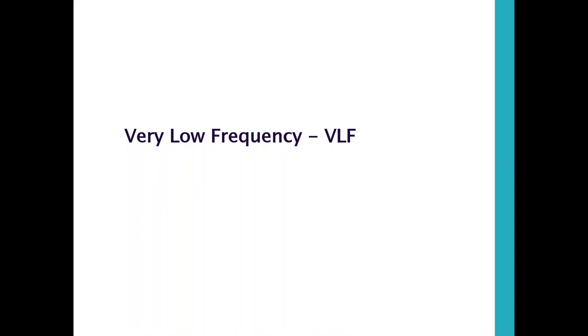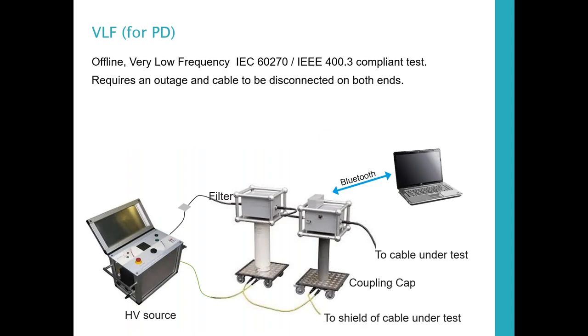So we're going to look at, at this point, some direct-connected offline testing. And we'll start off with the very low frequency VLF test. It tends to be one of the most common tests that are being used in the industry right now as far as offline tests. And there are reasons for that. But basically, if we look at the equipment and the setup of it, we've got a filter, we've got a coupling capacitor, we've got a high voltage source, we've got a connection to the cable under test, and then a connection to the shield of the cable under test to give us our return path.